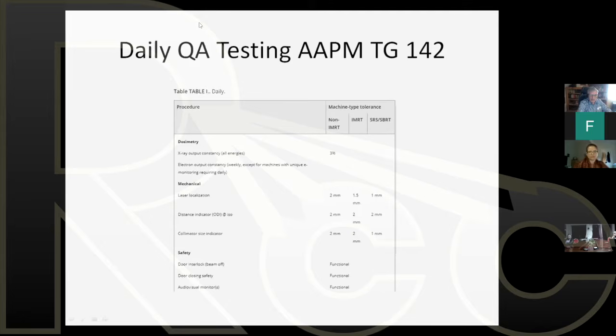Dosimetry, which we'll cover later on, has to do with X-ray output constancy. Now, the key word is constancy, not calibration. The therapists are not testing the calibration of the machine. The therapists are making sure that the output is within a range that the physicist has set. So that range is kept to 3% of a value that the physicist determines. And if the output falls within 3%, then the machine, at least from a constancy point, is okay to use. The radiation output falls within a range that's been established by the medical physicist. That has to do with both X-ray and electrons.